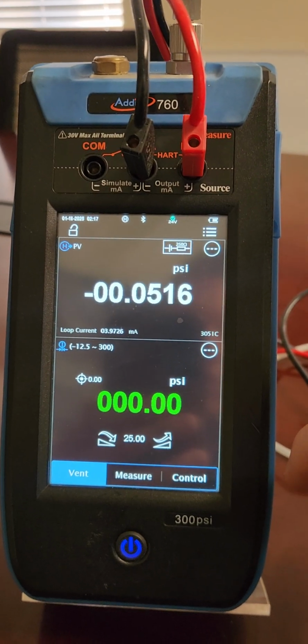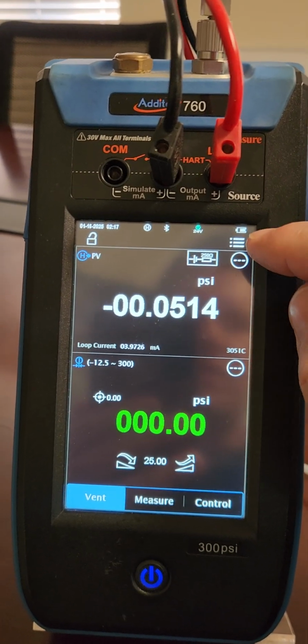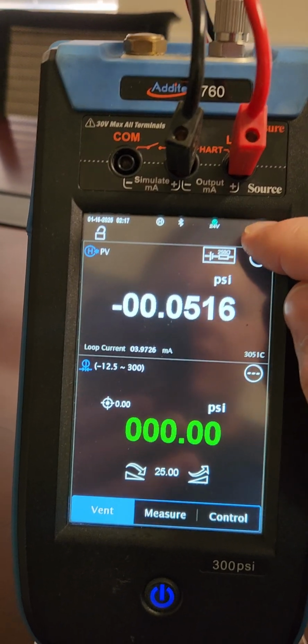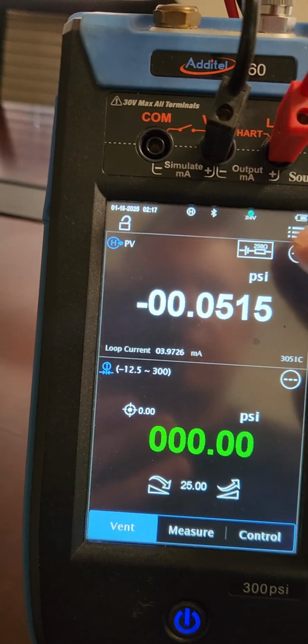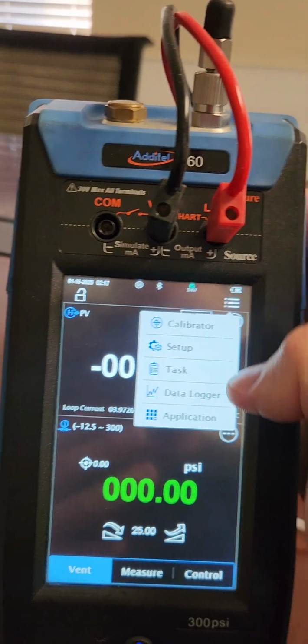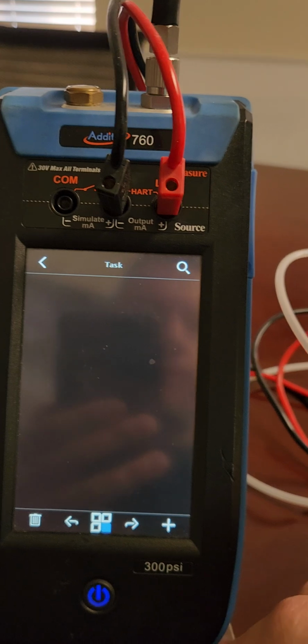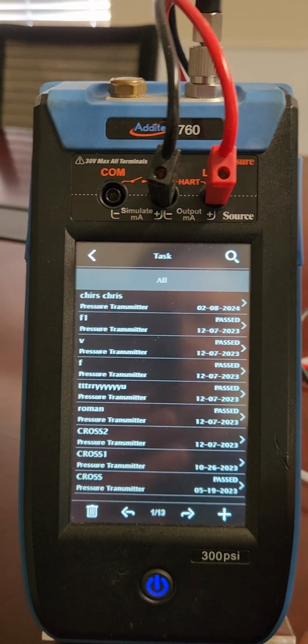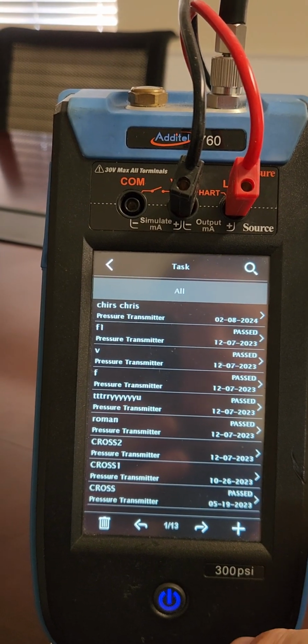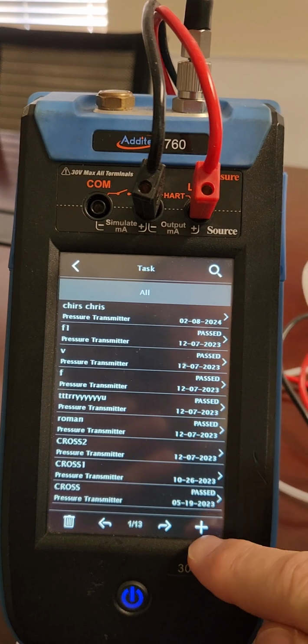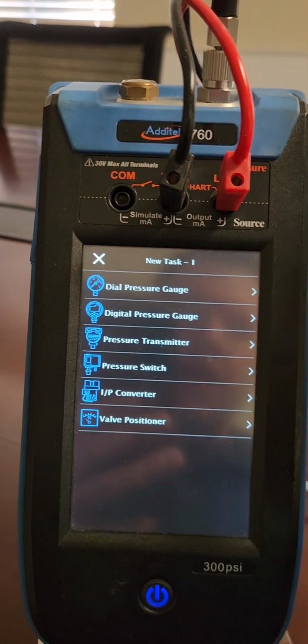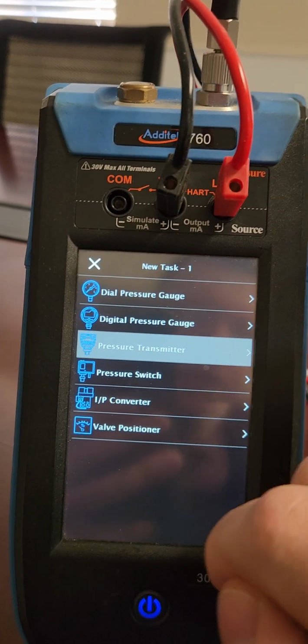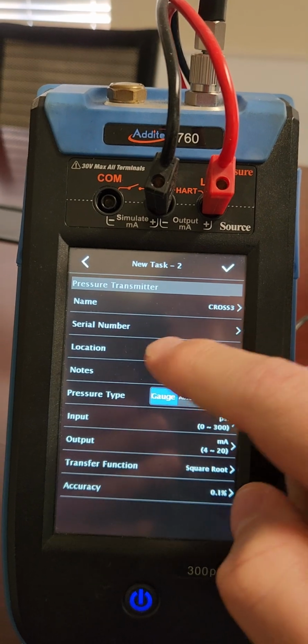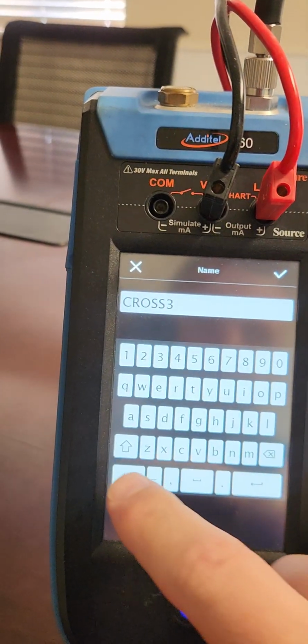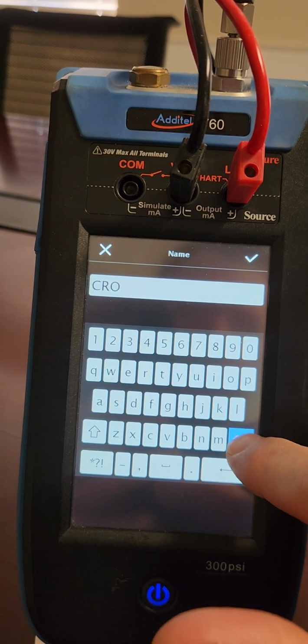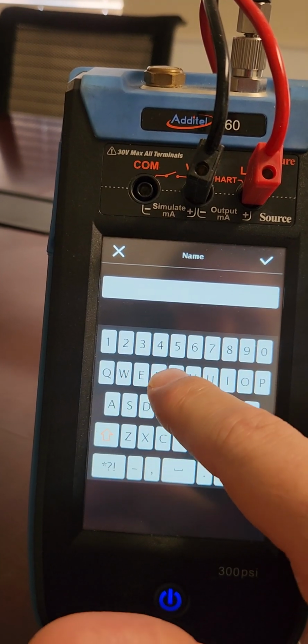So what you can do to calibrate this is you have an automated feature in here. If you hit your menu, you go to the task function, you can write a procedure for calibrating this. So we're going to add a new one, so we'll hit the plus. This is a pressure transmitter, so we'll select that device. You can name it. So we'll just name it test.